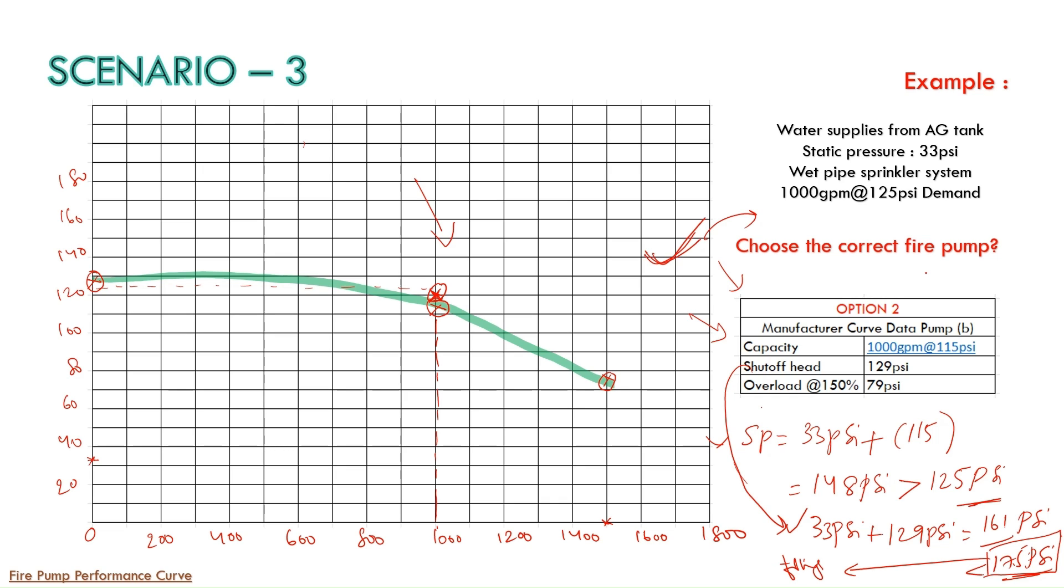But one more thing I want to highlight to you. Previously I told that based on this curve, straight away it can be rejected. In case if the static pressure is zero, see if the static pressure is zero, then zero plus 115 psi will be 115 psi only. So at 1000 gpm is 125 psi required. That is why we can reject this pump. But in our case, we have static pressure 33 psi, so we can select this Option 2.